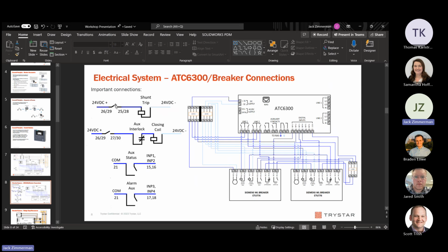So let's say we have under voltage, the voltage drops off from the utility line. Then likely this switch would close and activate the shunt trip. When you have 24 volts across the shunt trip, it opens the breaker. There are two of these logic forms per ATS because we have one on each breaker. All it's doing to activate the shunt trip is closing a little relay on the controller itself. That lives right here and gets connected right in there.